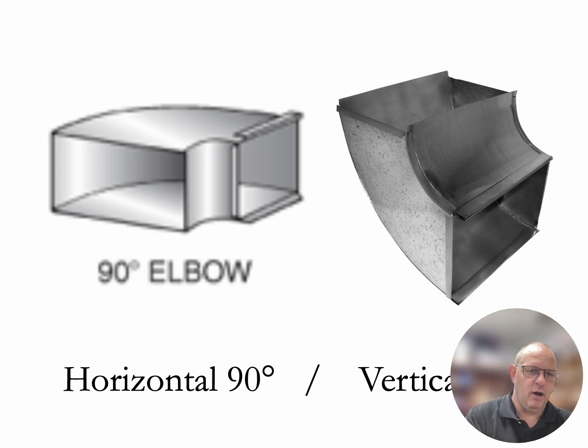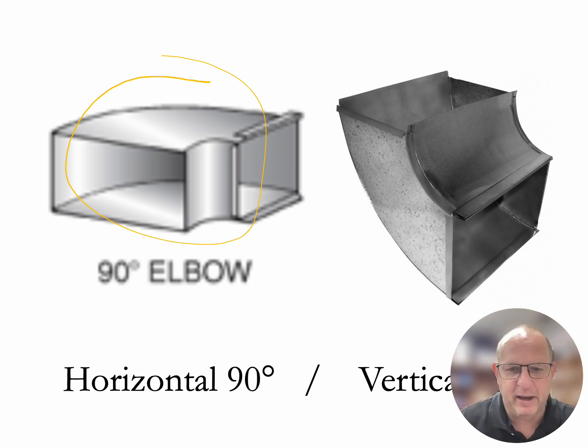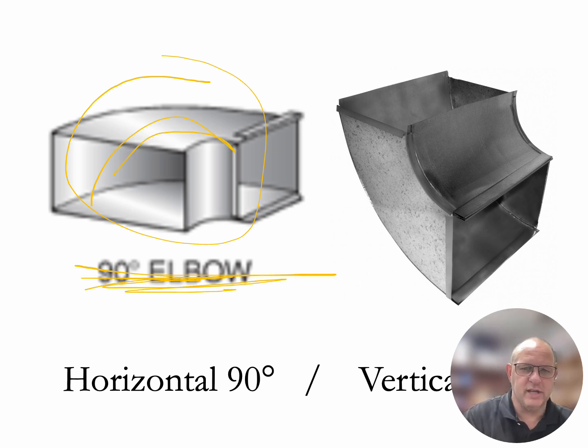Now, this 90-degree elbow here that we're looking at, if you were to lay it flat on the ground, you would notice that it is in a horizontal aspect. So the 90-degree is going in a horizontal direction, and it is not going in a vertical direction like the other pipe is. So this pipe right here that would fit on a square duct coming in sections that are 8 by 16, 8 by 18, 8 by 20 will be a horizontal application. Okay, so our 90-degree is horizontal.